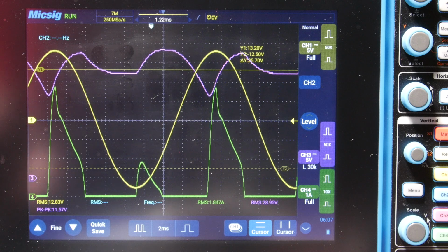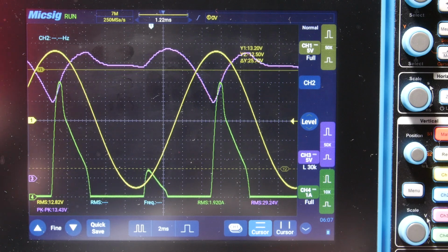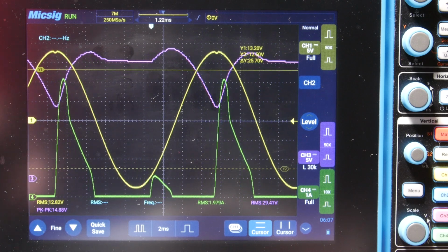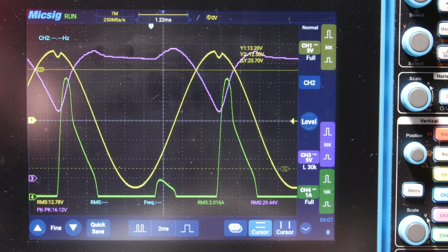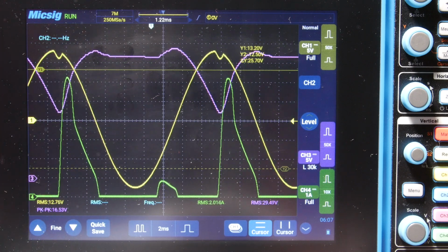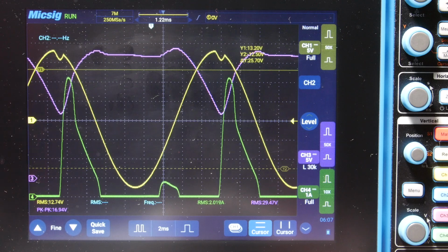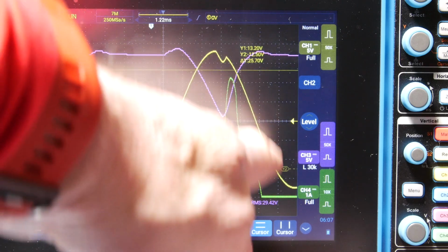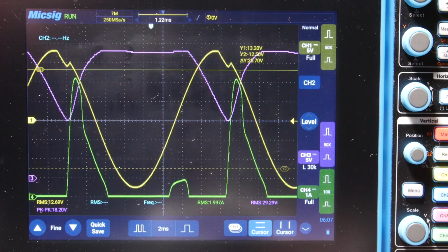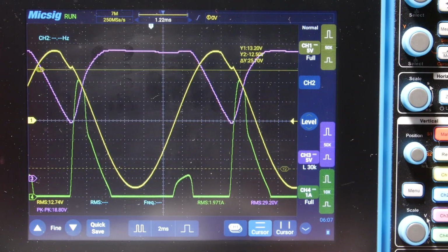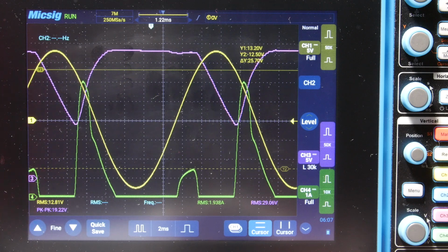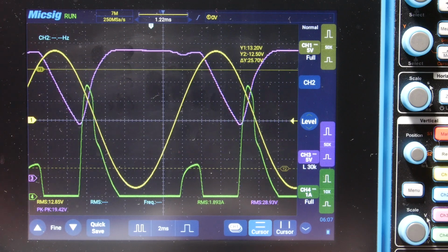I'm slowly changing the frequency. I'm at 60 hertz, 0.02 right now. And we're almost synced up. 60.01. Look at that. So every other pulse, we get a big one, and then we barely get one in between because our frequency is slower. I mean, we're getting a lot of ripple current. Some pretty high peaks.